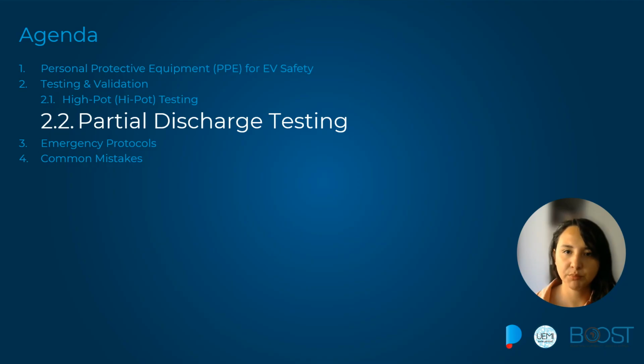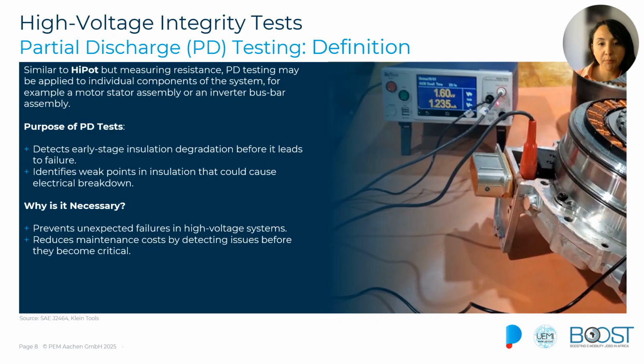What is the difference between the HiPot test and the partial discharge test? It is the ability to detect tiny electrical discharges that point out already very incipient faults that over long time and exposure can become catastrophic. So the partial discharge testing will measure those very small electrical discharges that might occur within a component's insulation. Unlike a full breakdown or a very high current flowing through the insulation, those discharges will not completely breach the conductors that we are testing. However, they are already warning signs that the insulation is not perfect and that it might fail in the future.